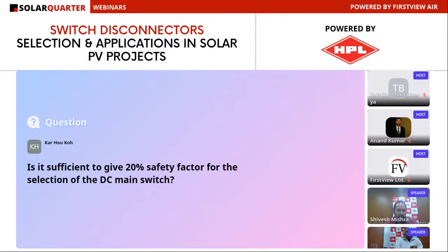Is it sufficient to do a 20% safety factor selection of DC main switch? As far as our switch is concerned, if 20% safety means you are using a switch of 400 amps and your current carrying is about 320 or 330, our switches should perfectly pass without any hesitation, even in enclosed condition. It should not be a problem, provided the size of the cable used in the system is adequate without any difficulty.